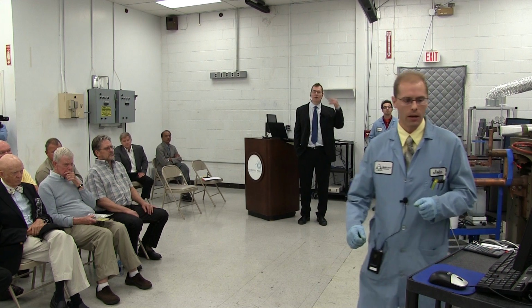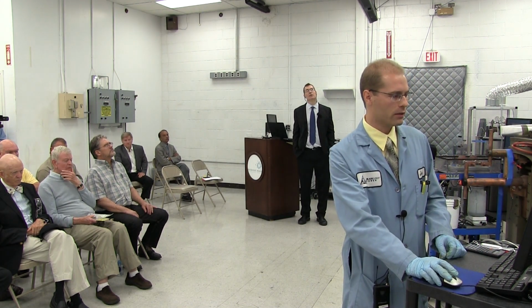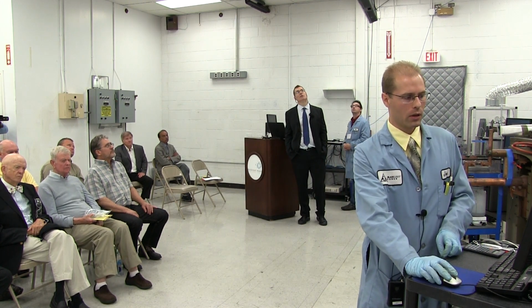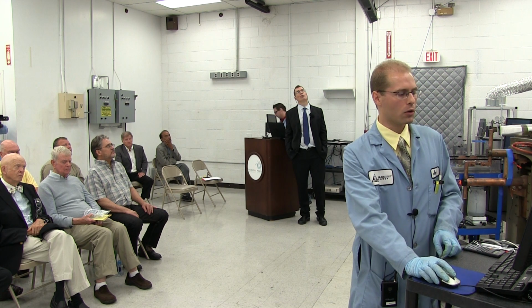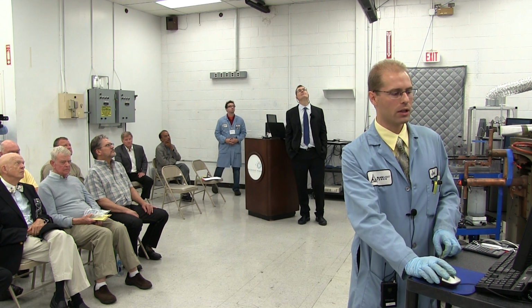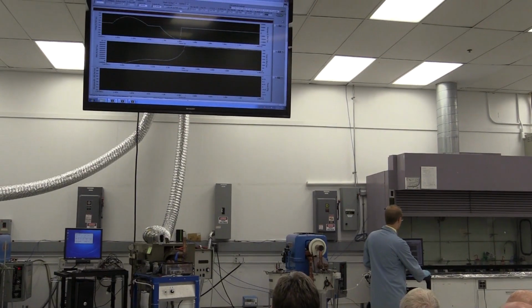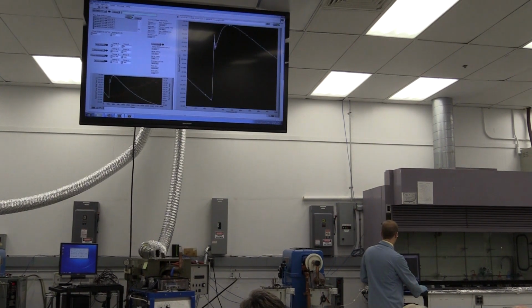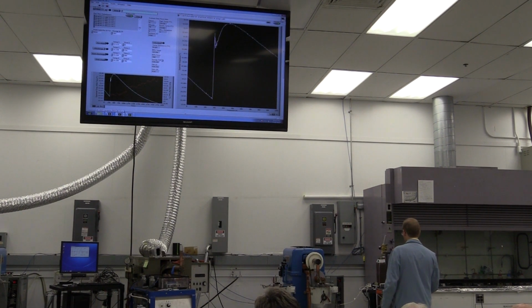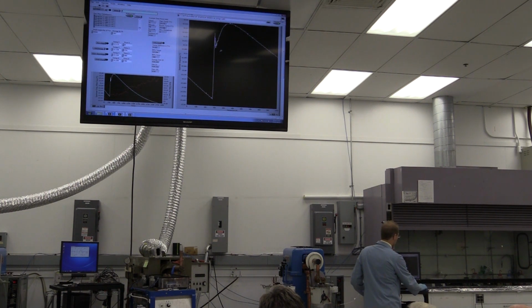And then essentially I initiated the sample while Randy was talking, so we can see from our previous VI the similar voltage in the red trace, the current in the white trace. And from that we can multiply the waveforms together to get the power and integrate to get the energy. At the time the sample initiated, 207 joules had entered the sample. And if we go look at the Parr VI, we can see this is the temperature trace being recorded by the thermistor. This thermistor's resolution is 1 millikelvin and repeatability is about 2 millikelvin. When I initiated the sample, you could see the previous slope of the room temperature going down. It suddenly rose in response to that reaction that took place. And then at the end of the reaction, the end point, the room temperature slope resumed.